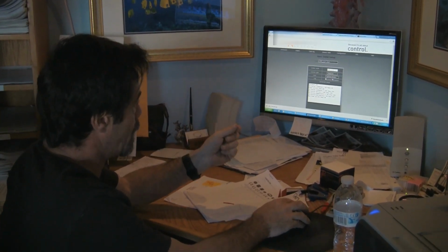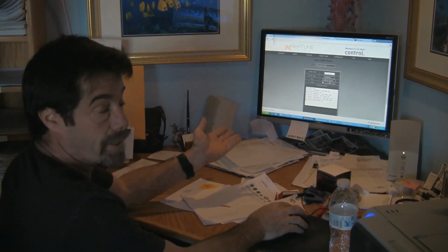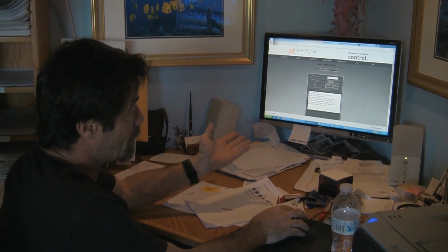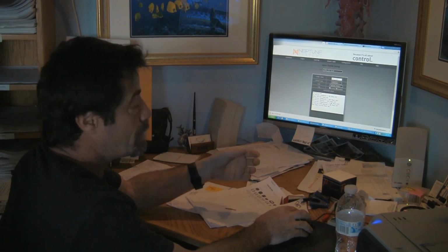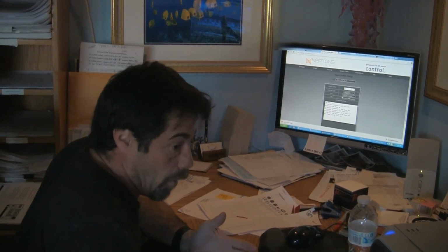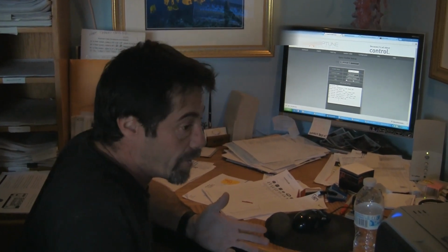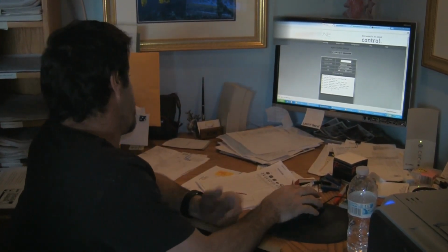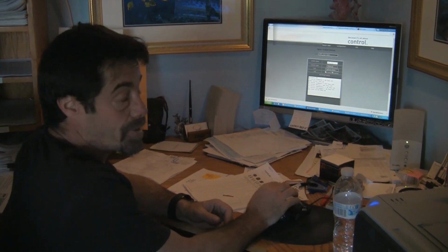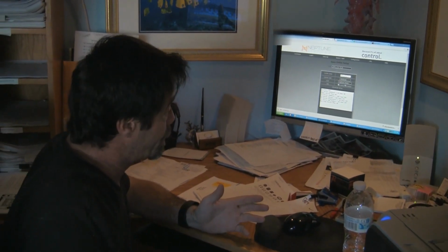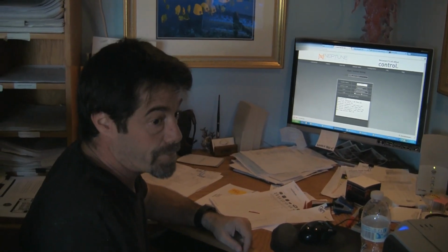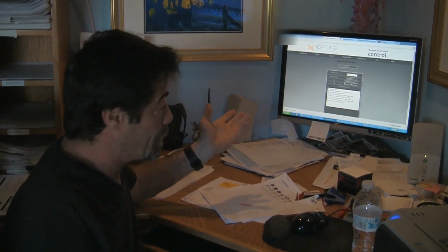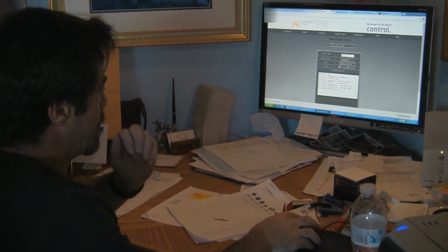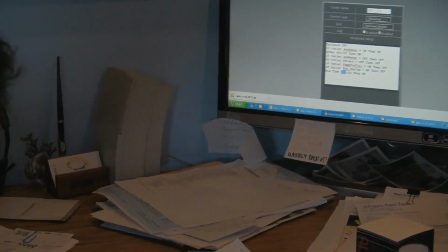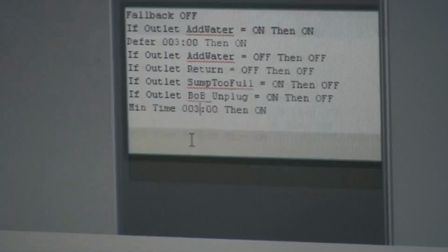When the outlet is off, the ATO turns off. If his return pump is off, we don't want the ATO turning on, so there's a line in there: if outlet return pump is off, then off. If the sump is too full, then the ATO turns off, because that could be a sign of water siphoning, which won't ever happen with this, or something else. No reason to have the ATO turning on if the sump's too full, which should never happen anyways. If the breakout box is unplugged, that little red jumper that we put in the breakout box earlier in the episodes, the ATO pump is off, because that could mean that the breakout box became disconnected. We don't want the ATO pump turning on. And in his case, the ATO pump will run for a minimum of 3 minutes. So I'm going to make that min time 3 minutes, so that the ATO pump doesn't just turn on for 60 seconds and then shut itself off.